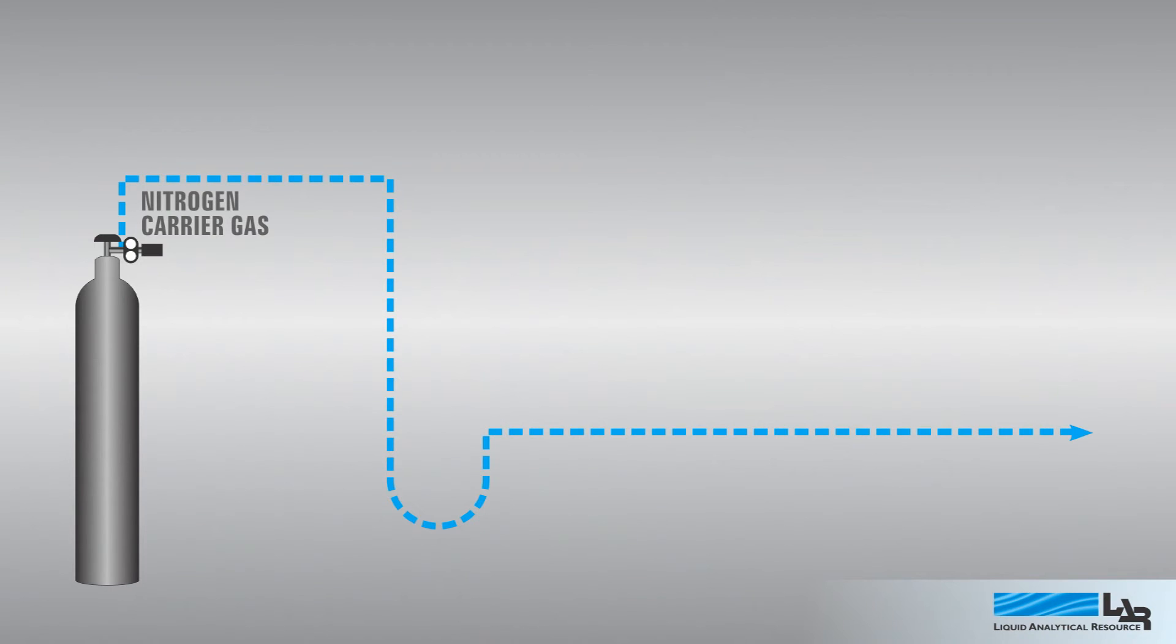During operation, a nitrogen carrier gas circulates continuously through the analyzer, and a small amount of air is added to provide a baseline of oxygen for the measurement. The nitrogen gas makes a circuit through the analyzer, where it passes through a high-temperature furnace.